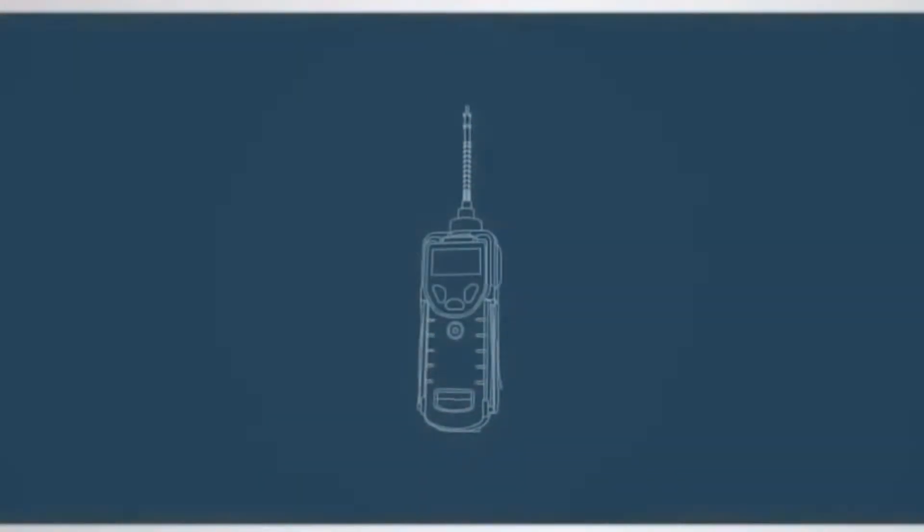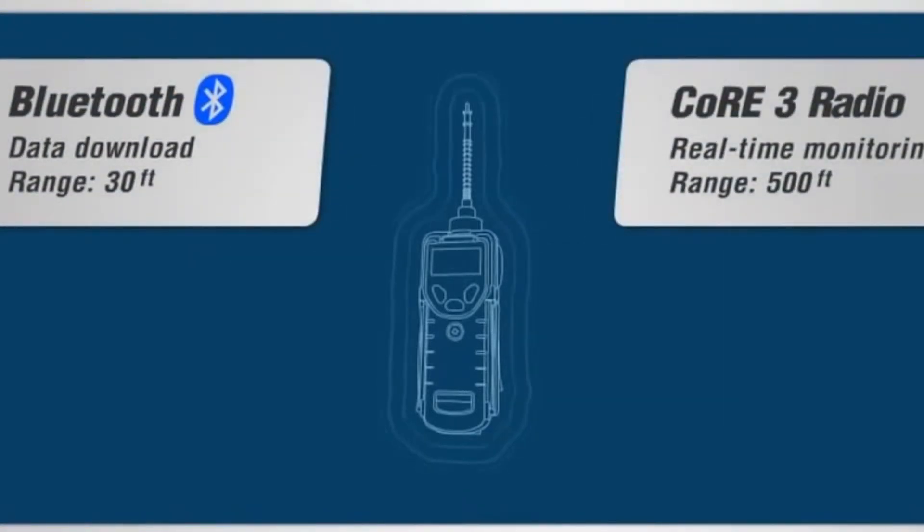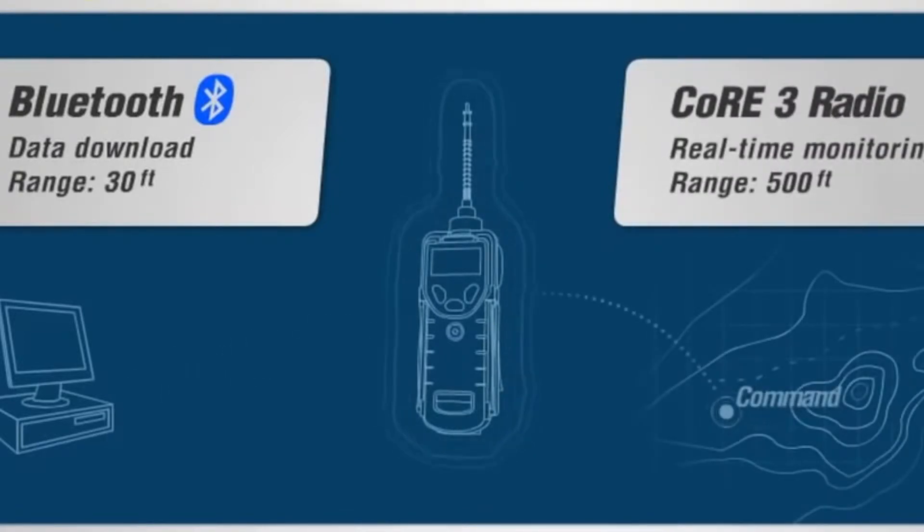The only handheld PID currently available with built-in wireless capability, the MiniRAE 3000 has two types of wireless transmission. Configured with a Bluetooth module, you can download recorded data to a nearby PC. The second configuration is a radio module built into your MiniRAE 3000 instead of Bluetooth, which allows you to transmit real-time data up to 500 feet away.